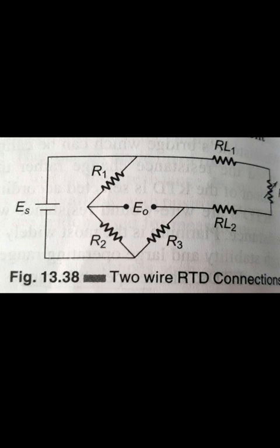requirements. Most of the temperature transducers are the resistance temperature detector, that means the RTD, the thermistor, and thermocouples. Of these, RTDs and thermistors are passive devices whose resistance changes with temperature, hence they need an electrical power supply to give a voltage output. On the other hand, thermocouples are active transducers based on the principle of the generation of thermoelectricity.